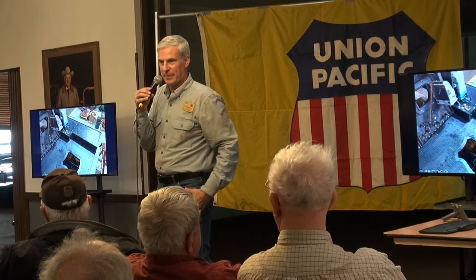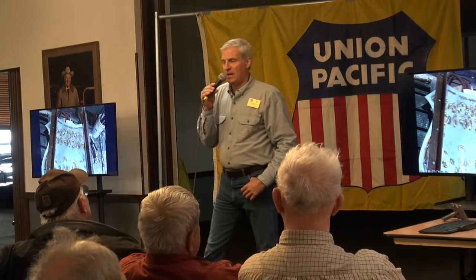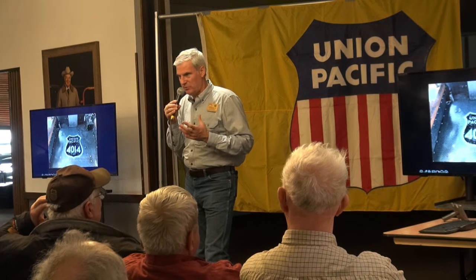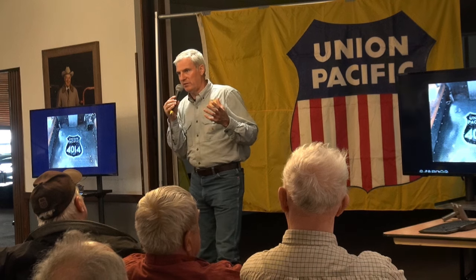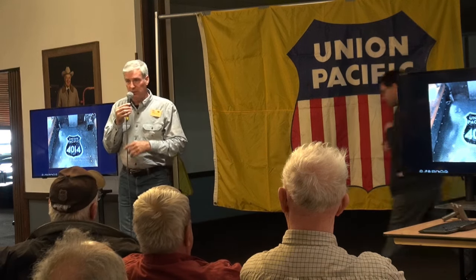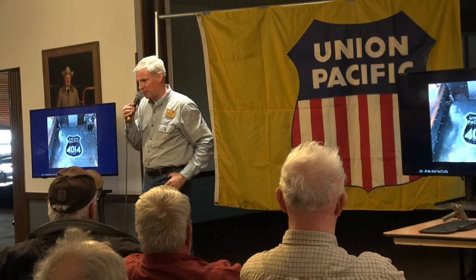Okay, sir. Yes, do you guys carry water purification with you? Is that how you deal with it? This question was, do we carry water purification? The answer is yes. So we have inline filters, which are maybe a little bit more than a glorified swimming pool filtration system. So we're taking out chunks, big stuff. Then we run it through a water softening system. So that's an industrial version of what you'd have in your home, where you run it through that water softening resin bed. And how that works is kind of neat, I'll just give you a real quick.